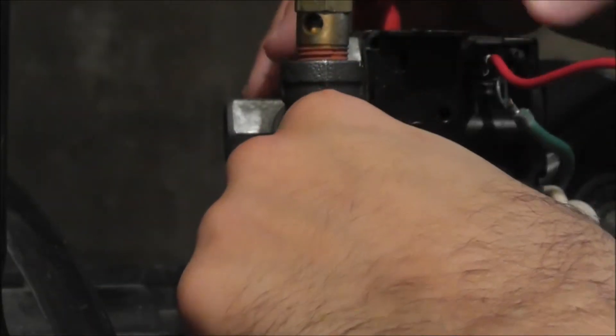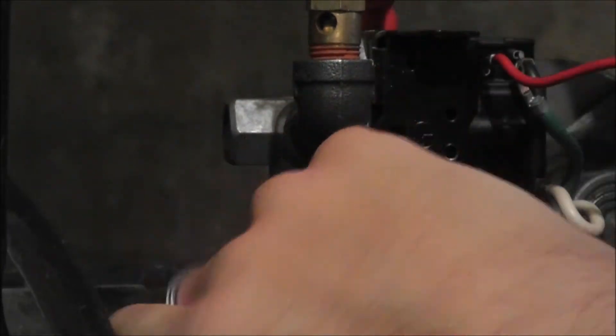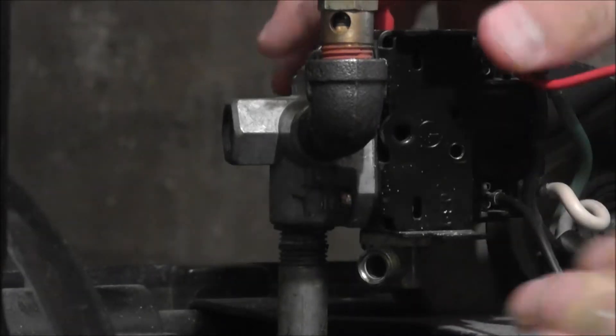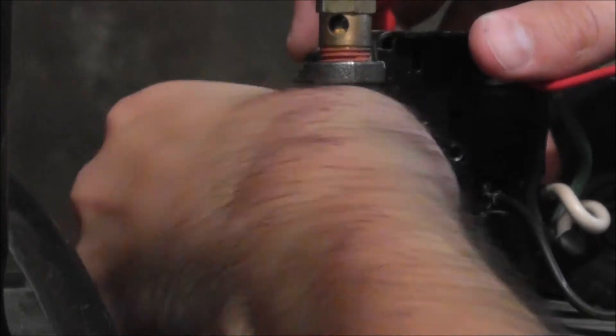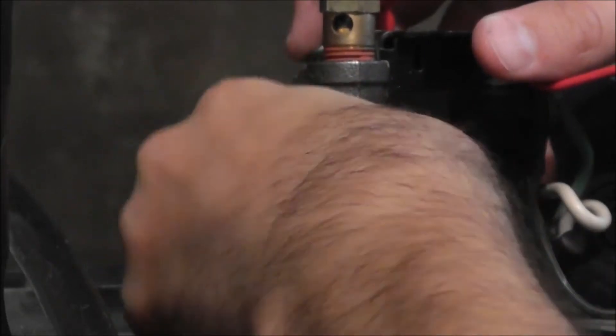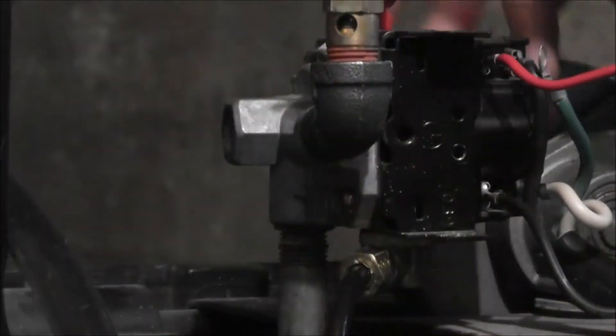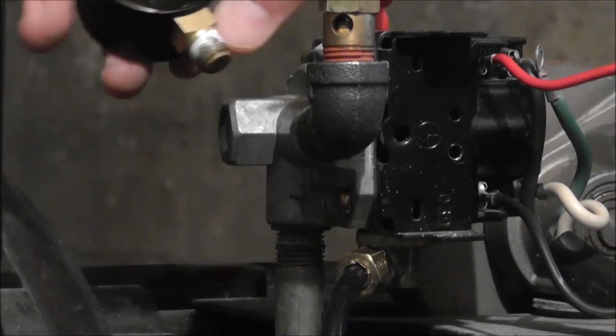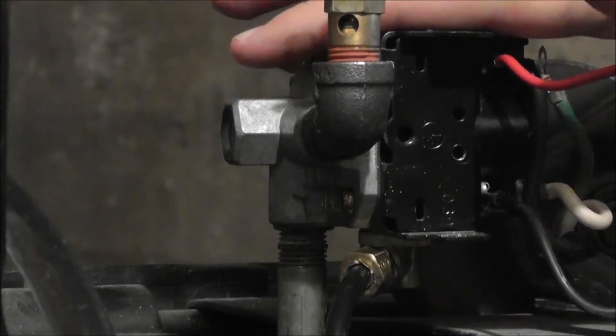So once you do have that installed, and again, I have the unloader line off here—it goes to the unloader valve and the pressure switch. You'll need to connect that next. Here you'll see the unloader valve, which unloads all the excess pressure off the line. Once it shuts off, simply attach that back with a quarter-inch compression nut onto the valve itself, and there you have it. And then you want to simply reattach your pressure gauge and all the components that you had taken off.